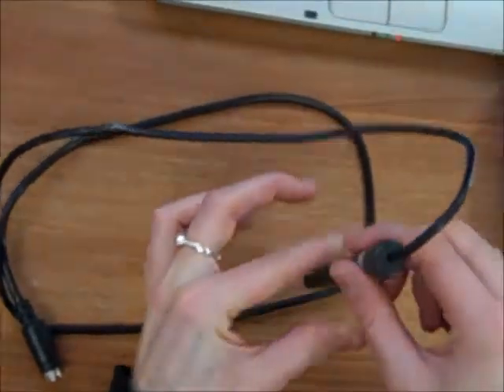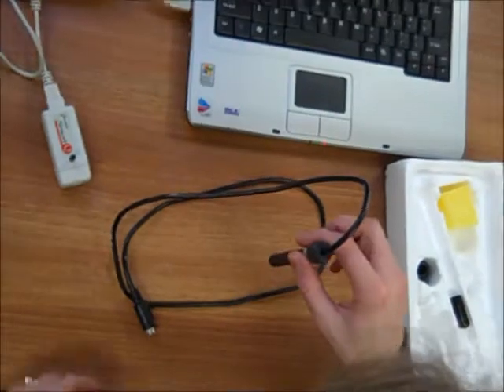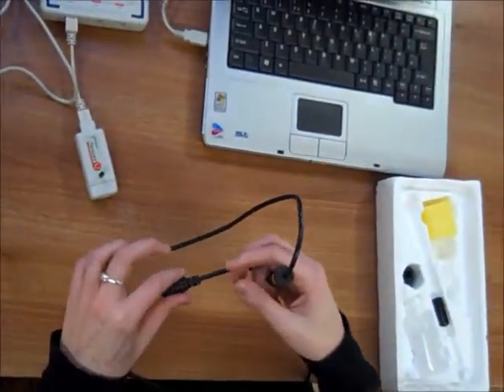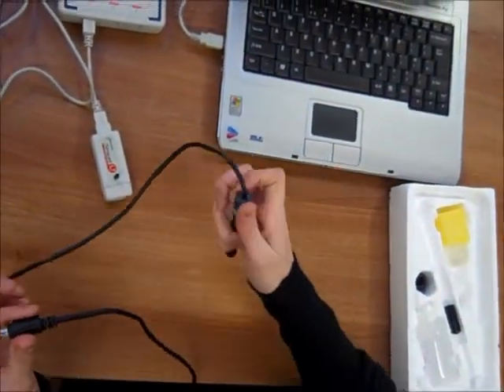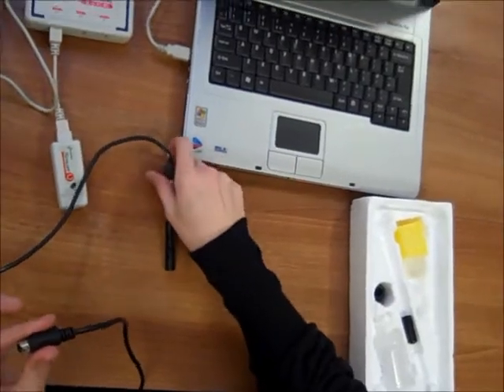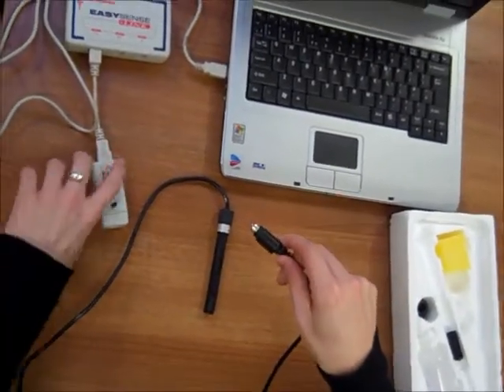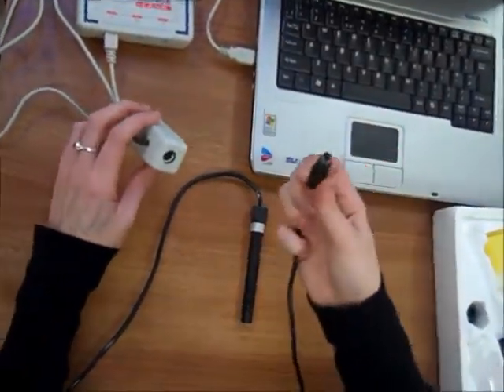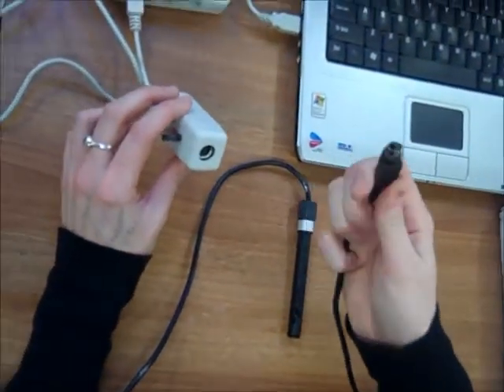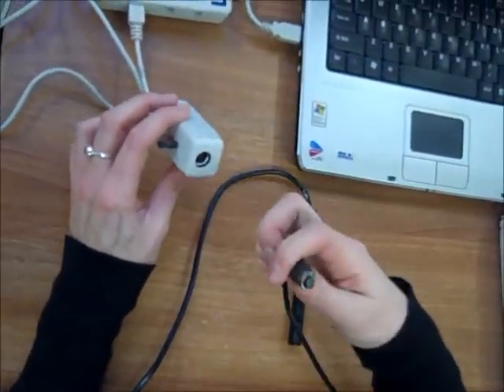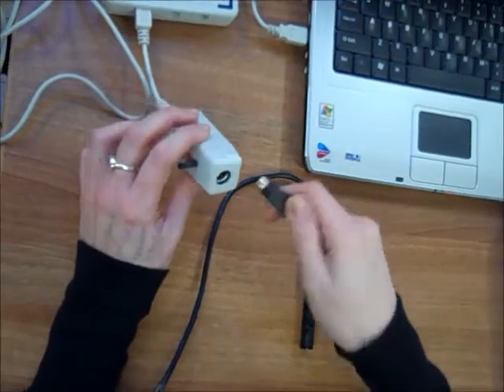Okay. Now, ideally, this needs to be kept upright for at least 5 minutes in order for it to settle. But I don't have time to do that. So we're going to connect the oxygen probe into the oxygen adapter. And that is done using these two. This one doesn't have a flat base on here, so you have to be really careful which end the prongs need to go in.